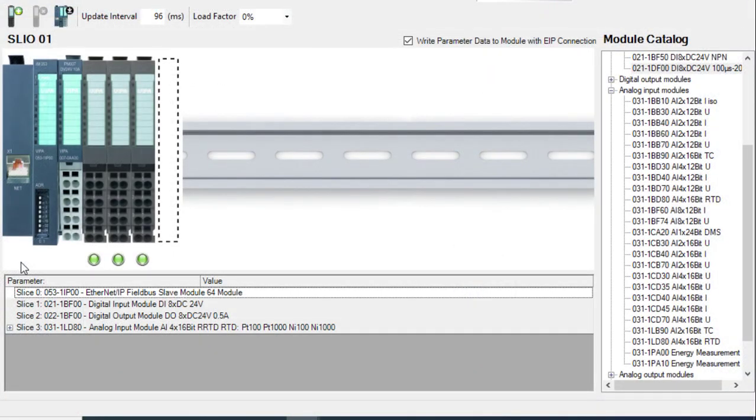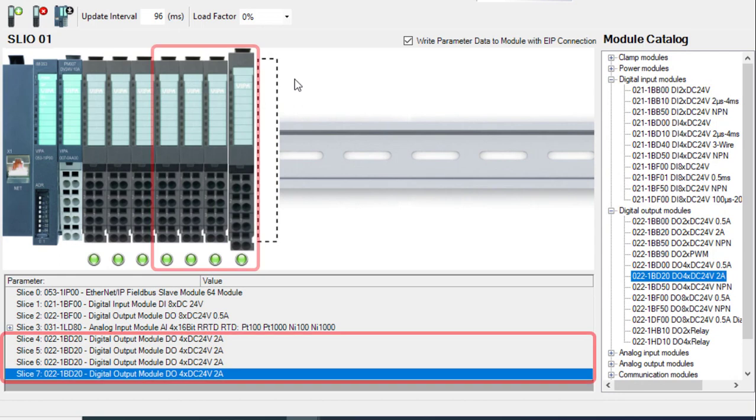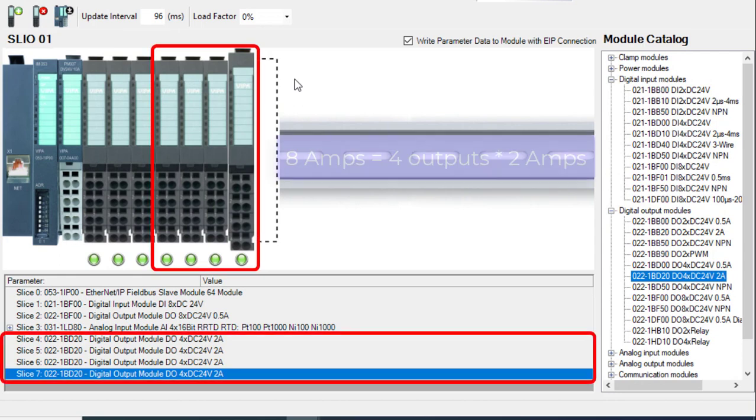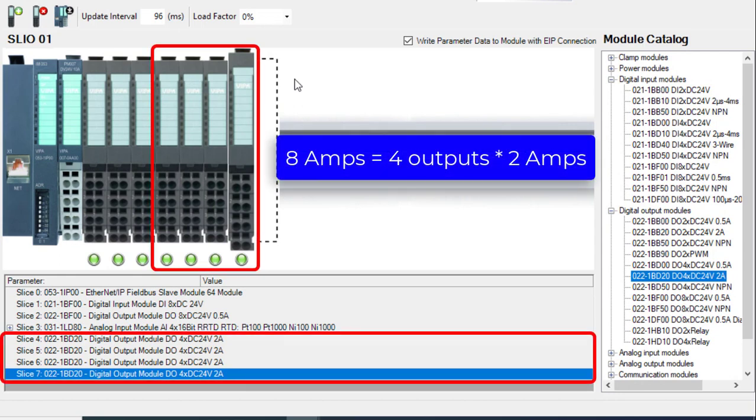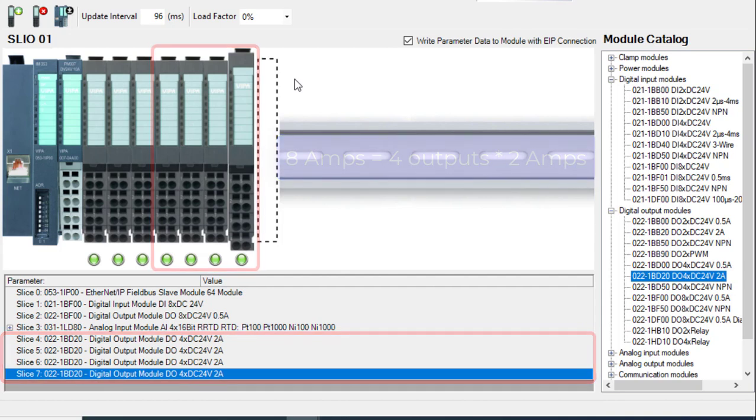Each slice draws power from the interface module. Some slices can draw a lot, like these digital outputs, which can consume 8 amps, because there are 4 outputs, each consuming up to 2 amps per output.